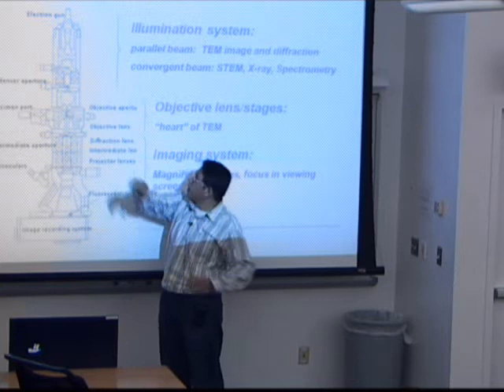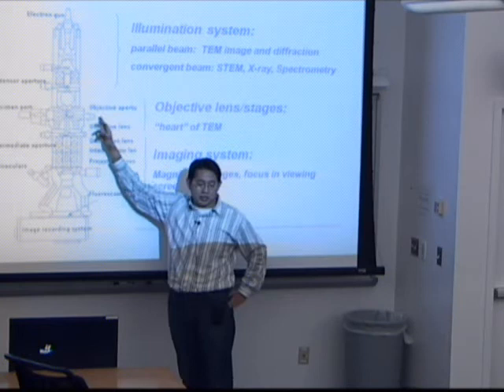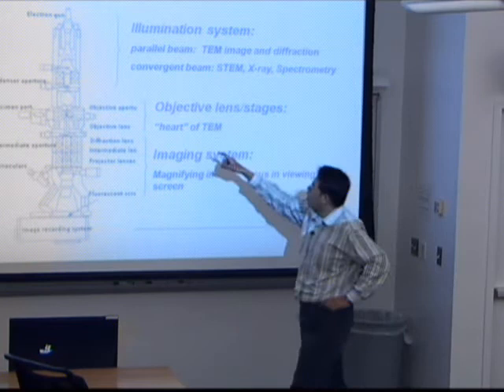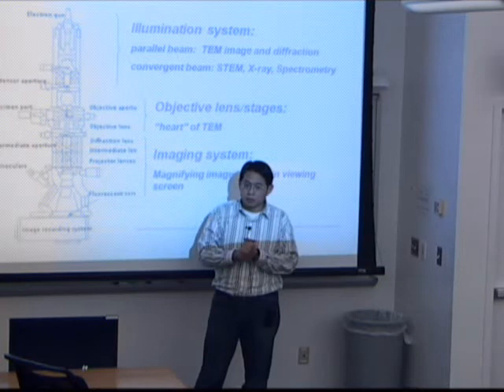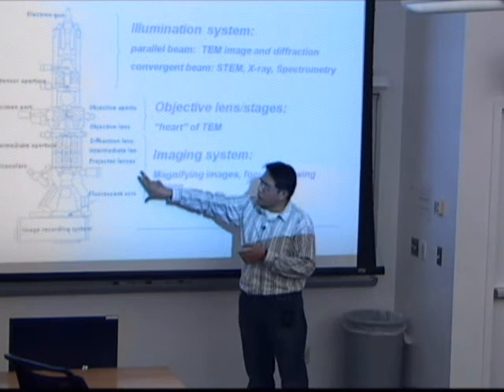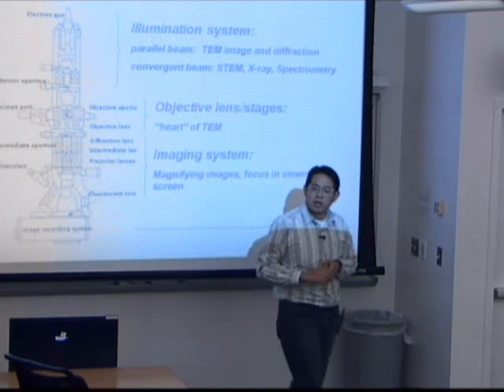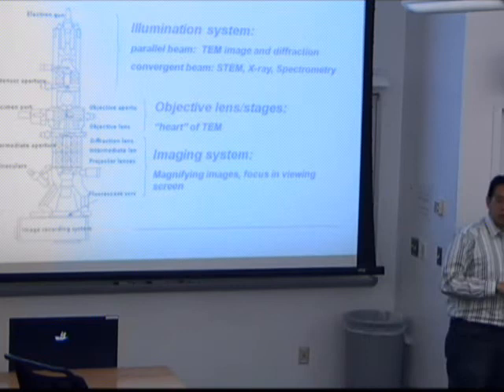The second part of the TEM is a very small part, about tenths of a centimeter deep, called the objective lens and stage. It includes the objective lens and objective aperture. It is very small but very important — it's called the heart of the TEM. Basically, in this part of the machine, you generate the images of the specimen. The third part contains many lenses: intermediate lens, diffraction lens, and projector lens. The main purpose of those lenses is magnifying the image up to a million times magnification.